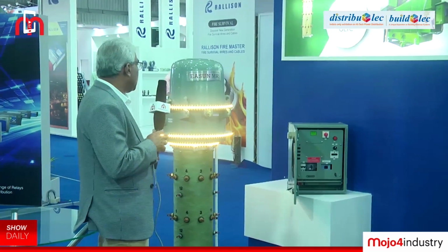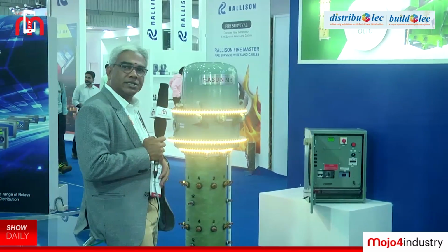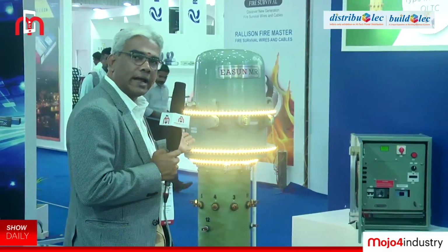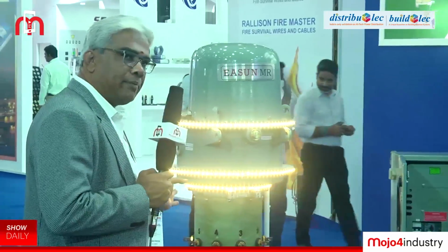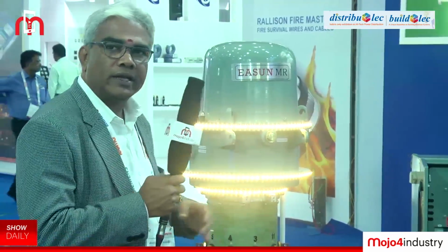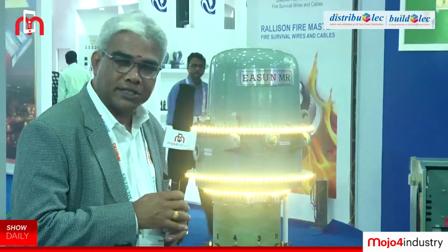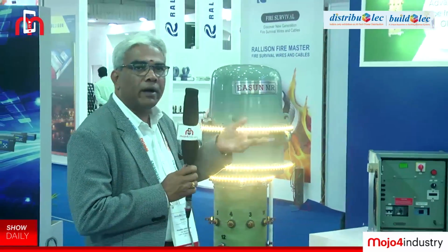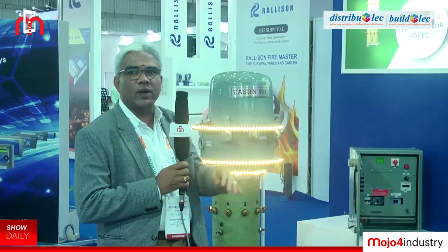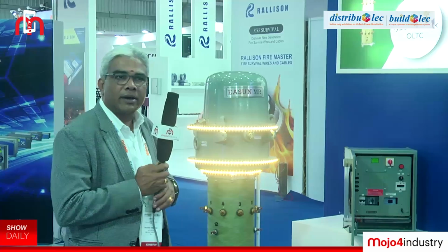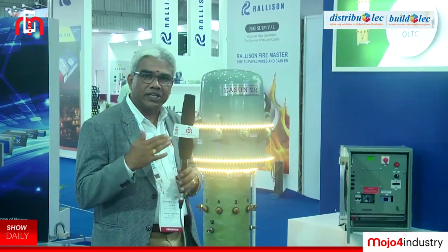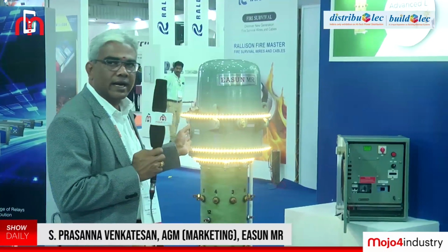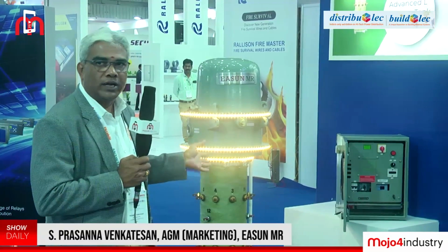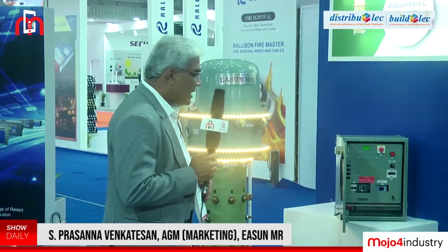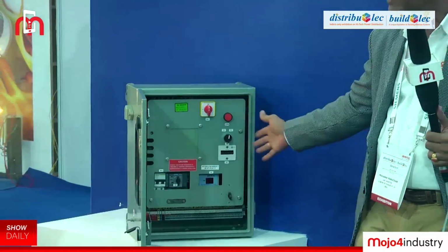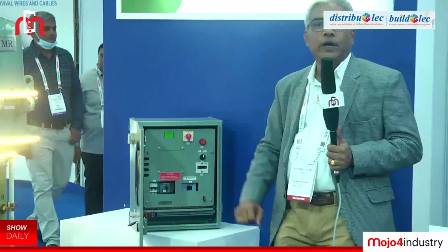This is another product from EASUN MR Tap Changers, produced in Puducherry, called L-type OLTC. This is highly useful for 11 kV and 33 kV distribution systems, where in the event of power failures or high voltage drops due to line loss or distribution voltage fluctuations, this tap changer corrects the voltage and delivers secondary voltage as smooth as 433 volts. We connect it from the control panel to the OLTC.